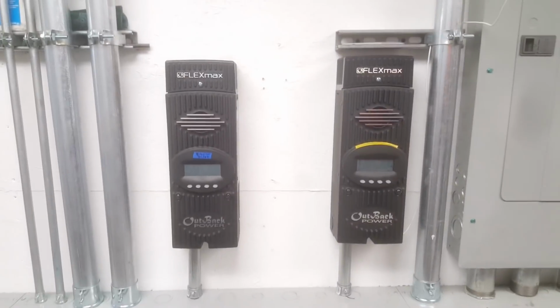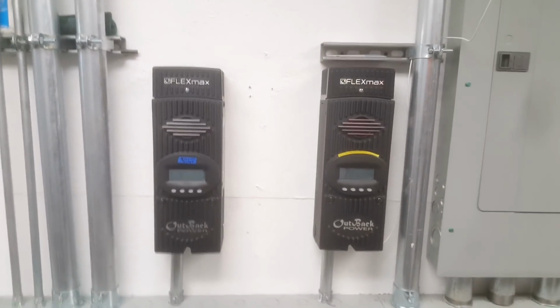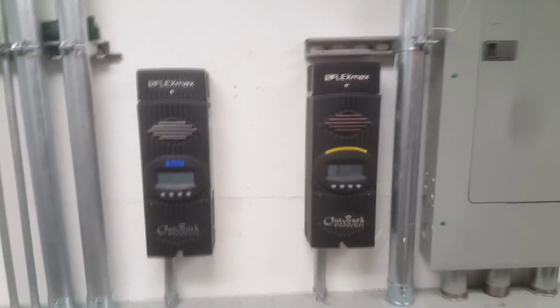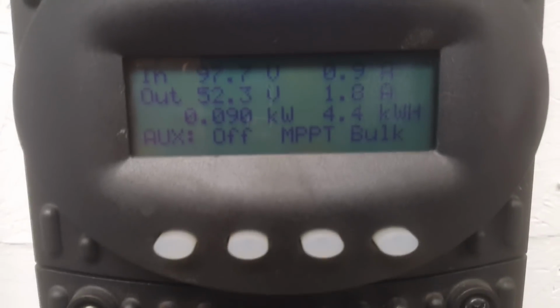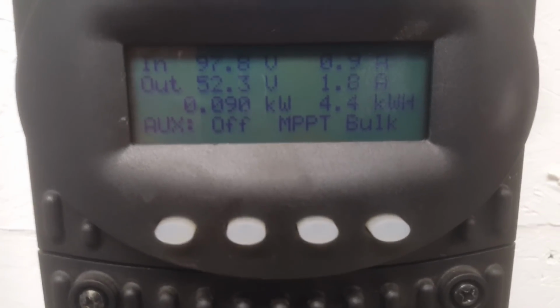These are my 2 Outback FlexMax 80 charge controllers. These go from the solar panel input to the batteries through these 2-gauge wires right here. What those do is regulate the energy coming in. As you can see right now, it's a cloudy day. I'm pulling in 97 volts at 0.8 amps, actually 0.9 amps, and I'm outputting 52 volts at 1.8 amps. So it's actually converting voltage to amperage to better charge the batteries. Now this is an MPPT charge controller, which means it's getting the maximum amount of power out of the solar panels.